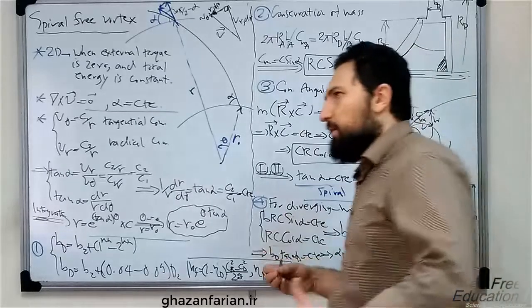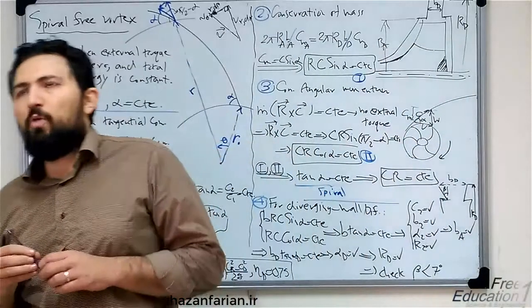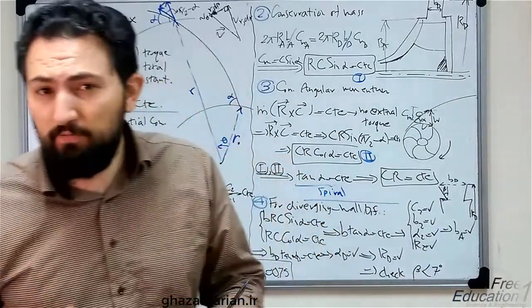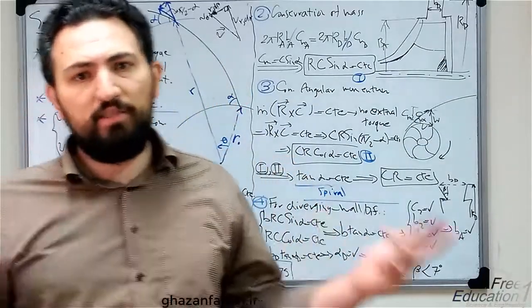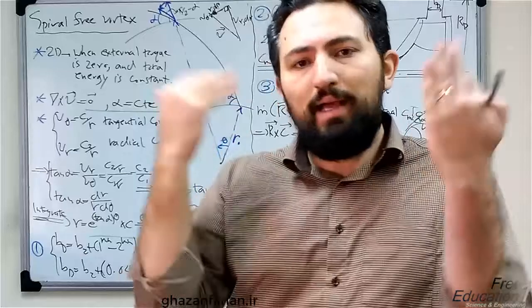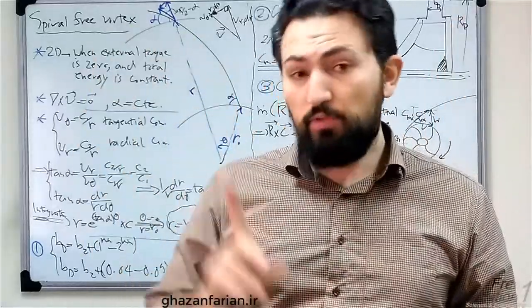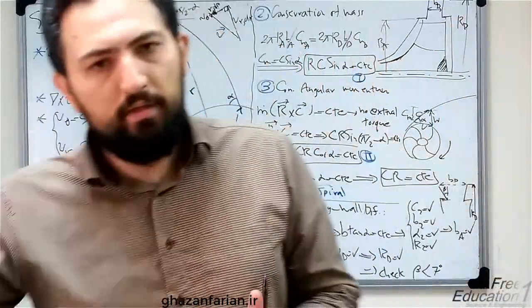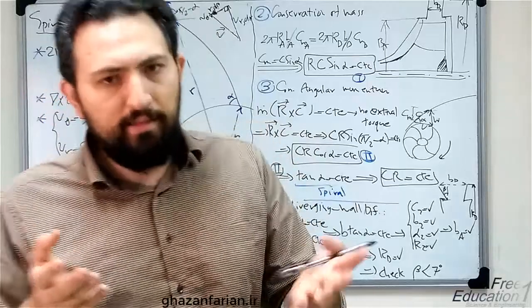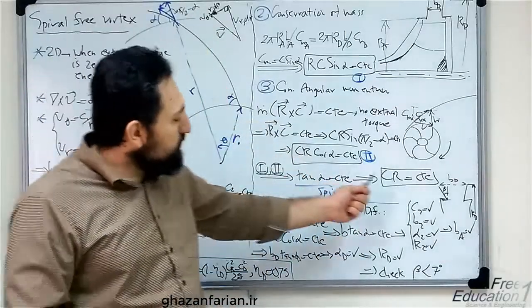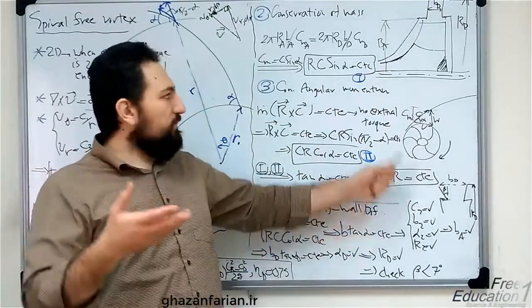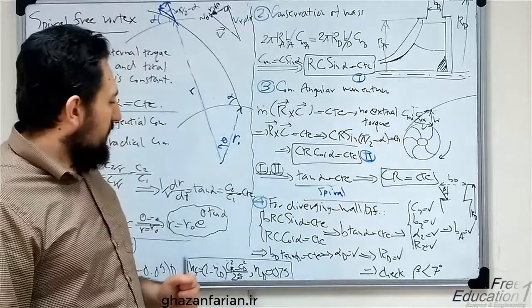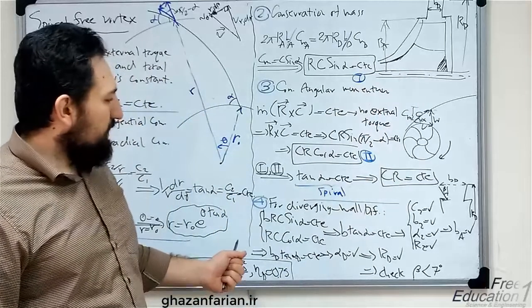By selecting, for example, that you want to reduce the magnitude of the velocity by 30%, the velocity at the outlet of the diffuser is 0.7 times the velocity at the inlet. Then you can easily compute the radius of the outlet of the diffuser R sub D.